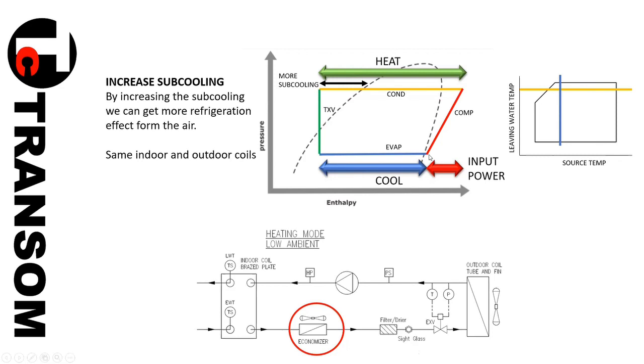Then the compressor builds it up and compresses it up here. And if you think of the wintertime, if you have condensation on your window, because it's steamy inside, the cold air on the outside window condenses that. So the condensing for a refrigerant is just a relative thing. So it's very hot for us, but for a refrigerant, it's still very low. So we go in and we cool it off until it turns 100% liquid again. And when we do the subcooling, we usually do like 5 or 10 degrees subcooling on a regular basis, just to make sure that there's no bubbles of refrigerant gas in there.